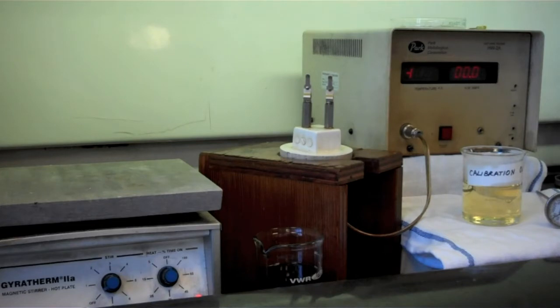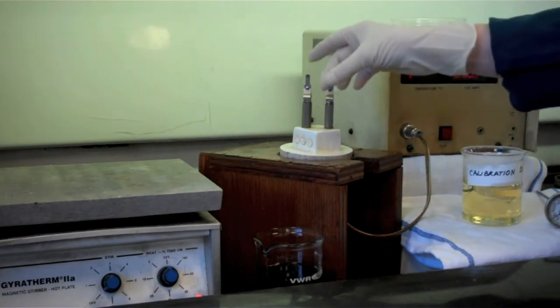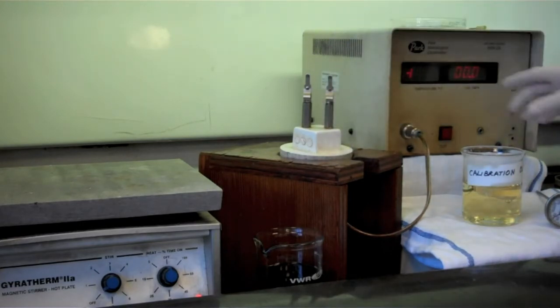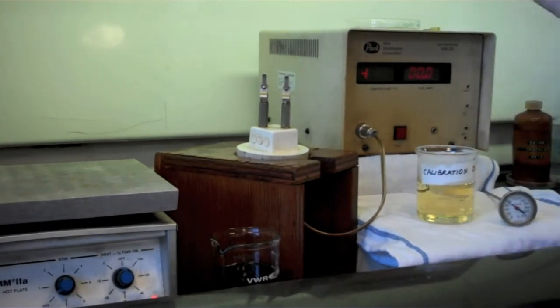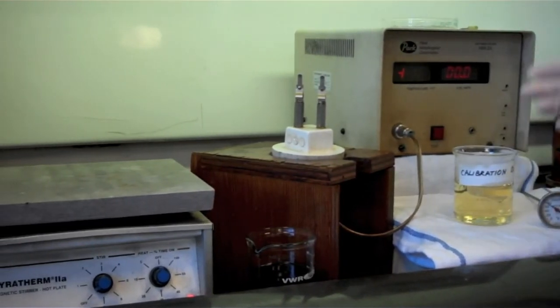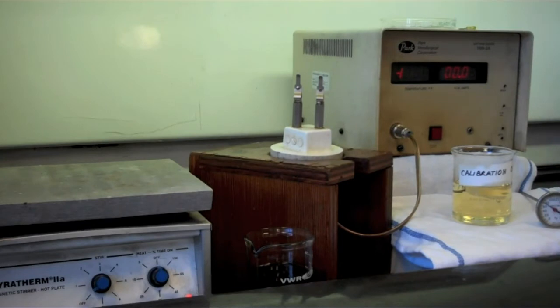The equipment necessary to run this test is the hot wire apparatus, the wire holding probe, a thermometer, a hot plate, a beaker, and of course the oils. Before testing an oil sample, we need to calibrate the apparatus. We are going to use an accelerated calibration oil as a reference.